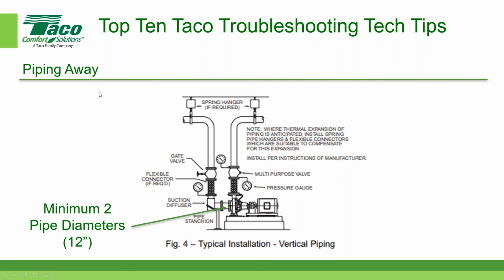And the other thing is we say pipe away from the pump. What we mean by that is, in this particular case, let's assume it's a rigid mount. There's a rigid pipe stanchion over here. There are flex connections up here. And all of this piping is done once the pump is placed physically with the base, and in this case, a housekeeping pad. Everything's bolted down and grouted and all that other kind of cool stuff. And then you pipe away from it, and then someplace over here, let me see if I can do this, before the pipe is connected to the system, let's say the system piping is over here somewhere. I'm going to exaggerate that it's a little bit off, a little bit higher. So whatever correction needs to take place, it needs to take place out here so that you get a smooth transition between the pipe connected to the pump and the pipe connected to the system. You don't want to put any strain on the actual pump configuration itself.